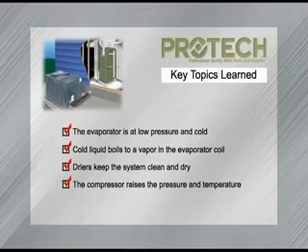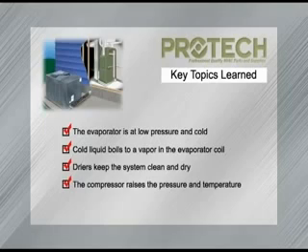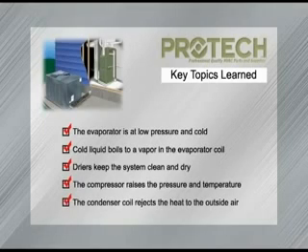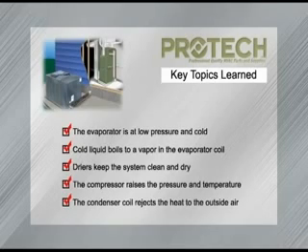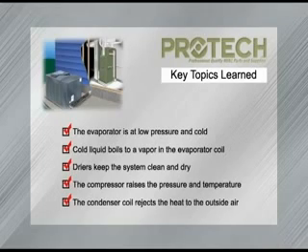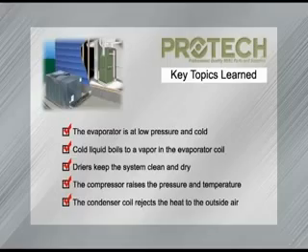We compress the vapor to raise the temperature of the refrigerant. The high pressure, high temperature refrigerant is pumped into the condenser coil — hot goes to cold — and the heat from the refrigerant is transferred to the outdoor air. The hot gas condenses to a liquid, which is then re-pumped to the indoor coil where, at the metering device, a pressure drop occurs and the refrigeration cycle repeats.